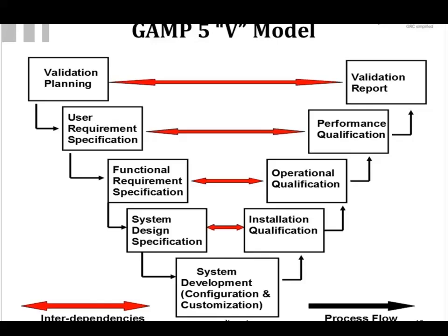A functional requirement specification might go down to a level of, I want to collect samples that are running on this particular instrument, and they are going to be within certain specifications as far as upper and lower limits for results. And you want to also make sure you capture the username and identity of the person doing the test. There are a whole lot of other details that you want to put in there.